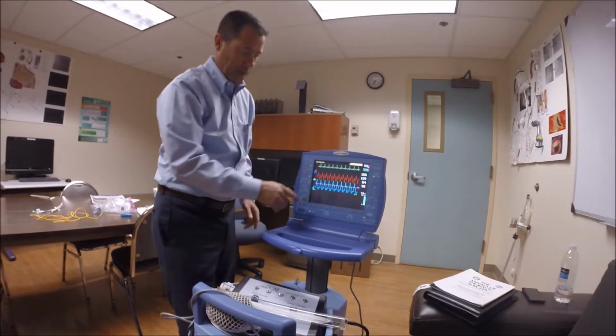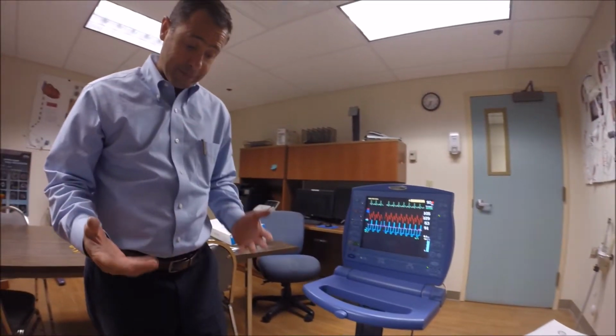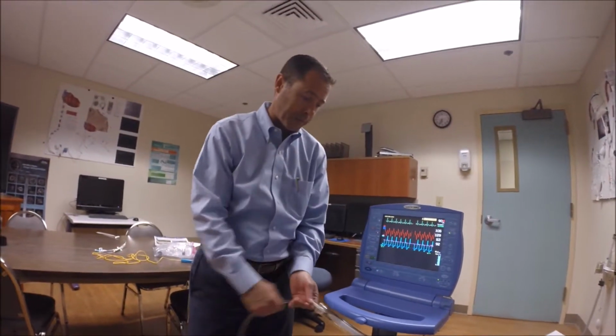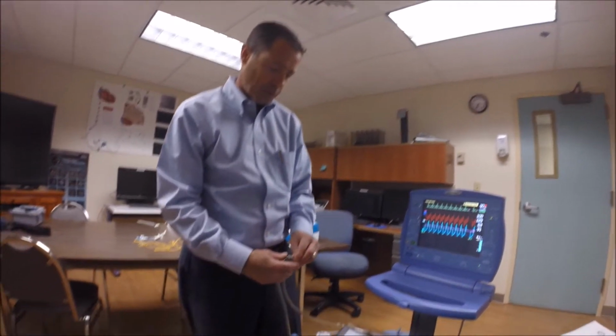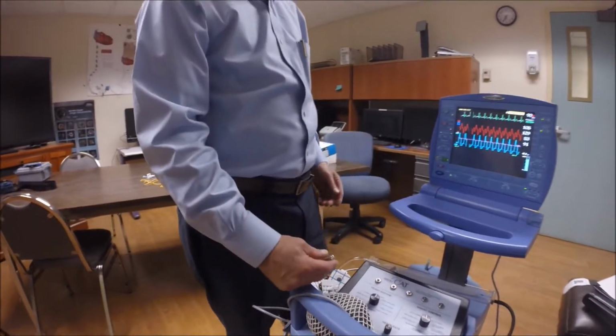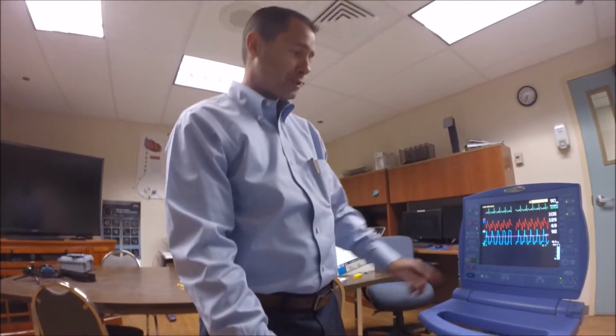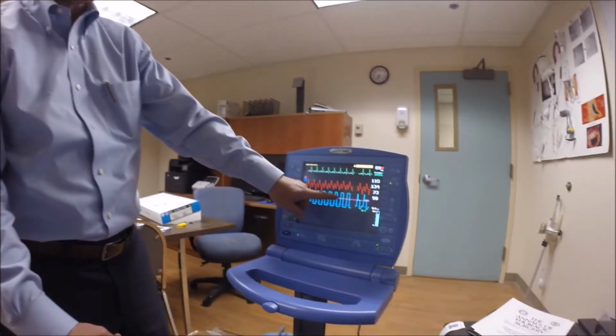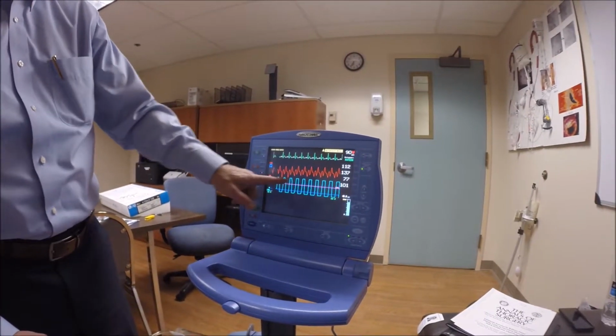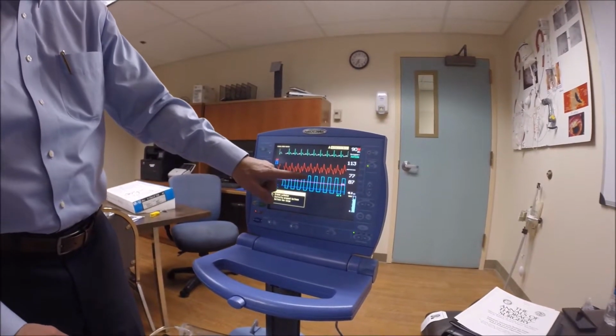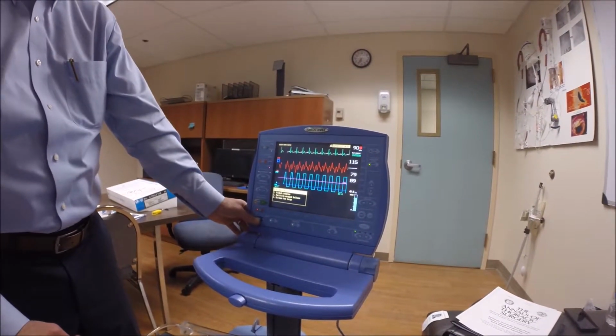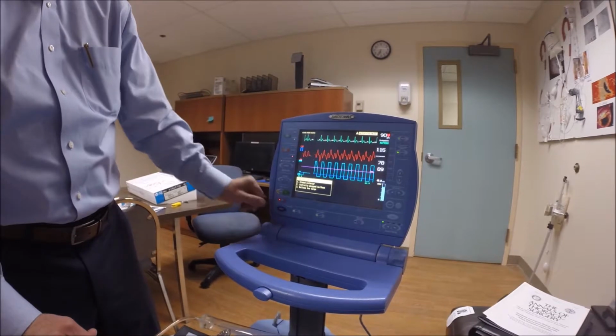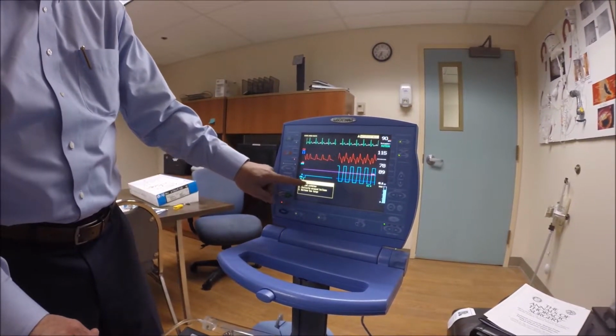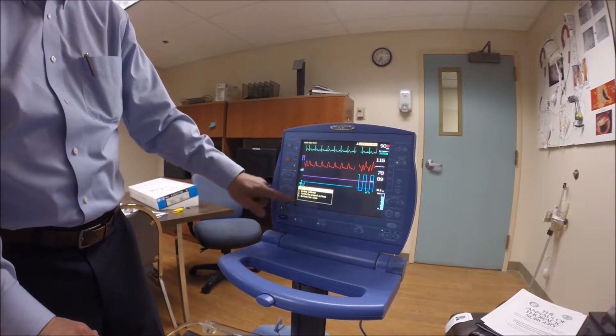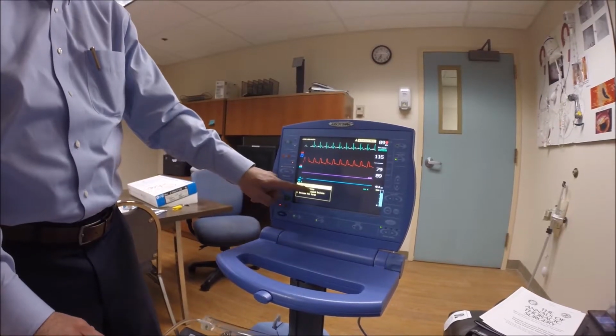Let's talk about printing a strip. When you do have an alarm, let's talk about that very quickly. One of the most common alarms is what's called the helium loss alarm. You'll notice my balloon pressure waveform is no longer a chair, but is squared off into a building. My reset button turns my alarm off. But you'll notice that the first thing under my high pressure alarm, the first thing on my laundry list to look at, is a kinked catheter.